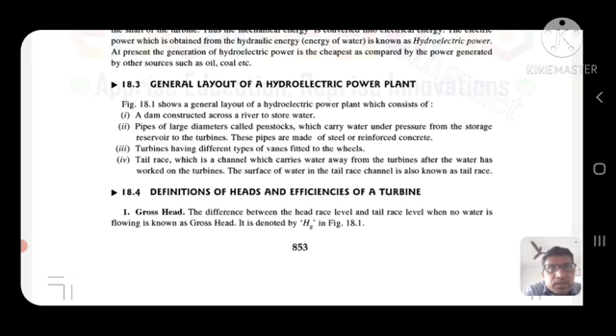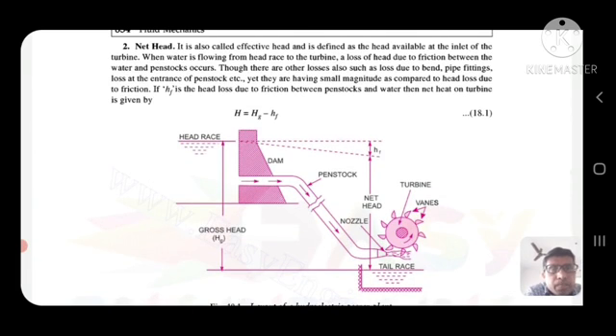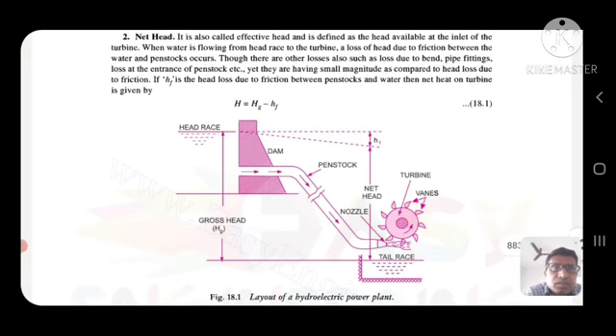The difference between the head race level and the tail race level, when no water is flowing, is known as gross head. Net head — also called effective head — is defined as the head available at the inlet of the turbine. When water is flowing from the head race to the turbine, a loss of head due to friction between the water and penstock occurs, though there are other losses such as loss due to bends, pipe fittings, and loss at the entrance of the penstock. Yet they are of small magnitude compared to the head loss due to friction.